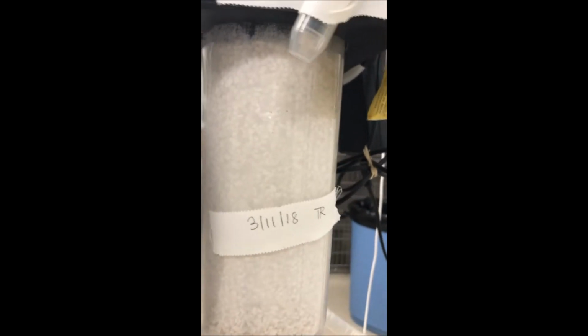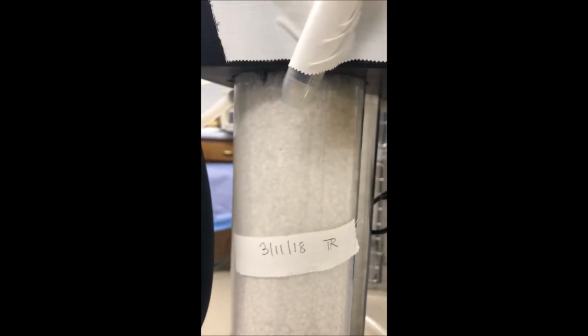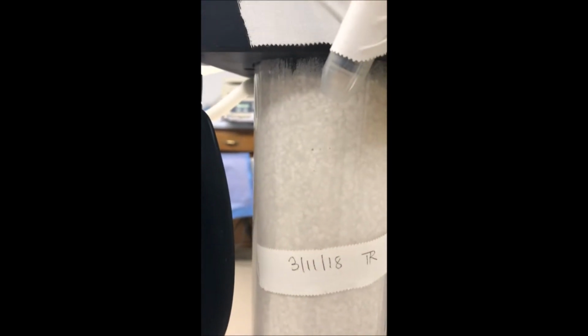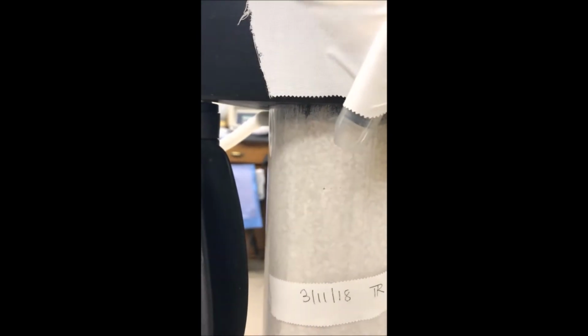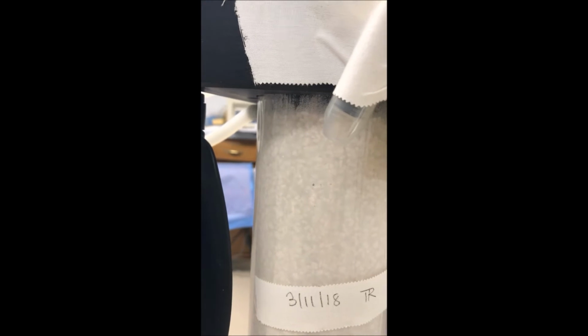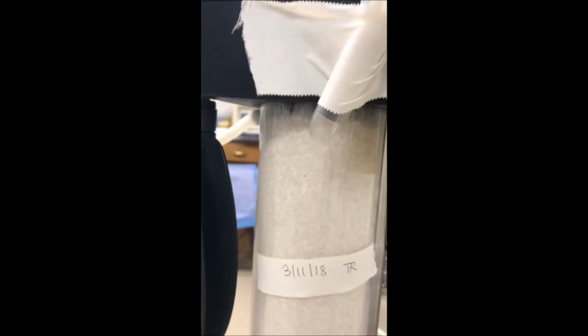If you see any purple in here, you need to go ahead and test your soda lime to see if it's still able to perform its job. You would open your canister, press on some of the tablets. It should crush fairly easily. If not, your soda lime needs to go ahead and be changed out.